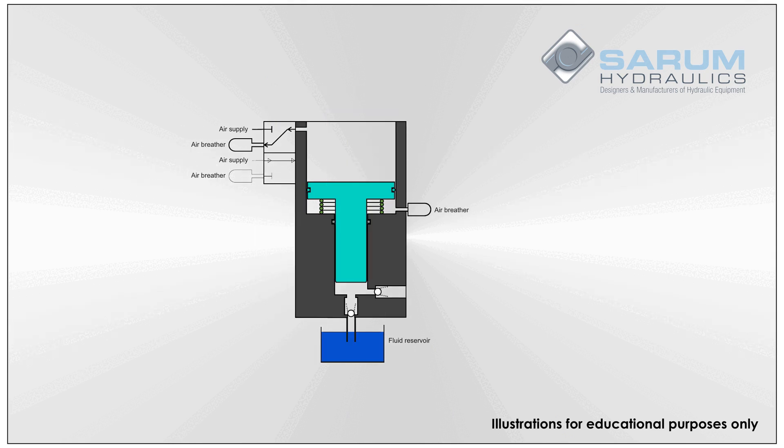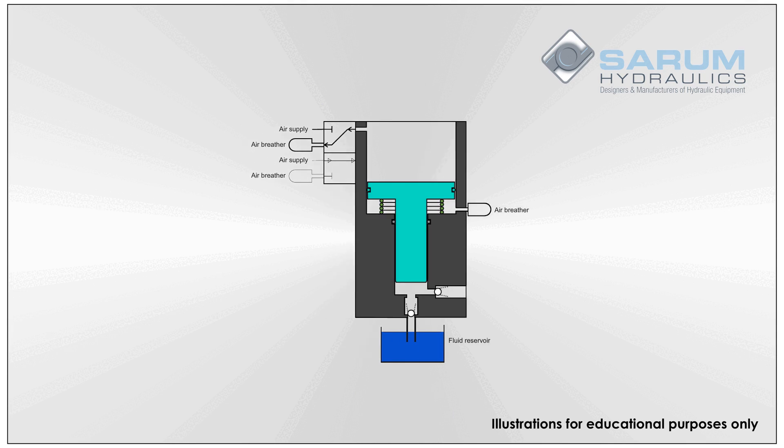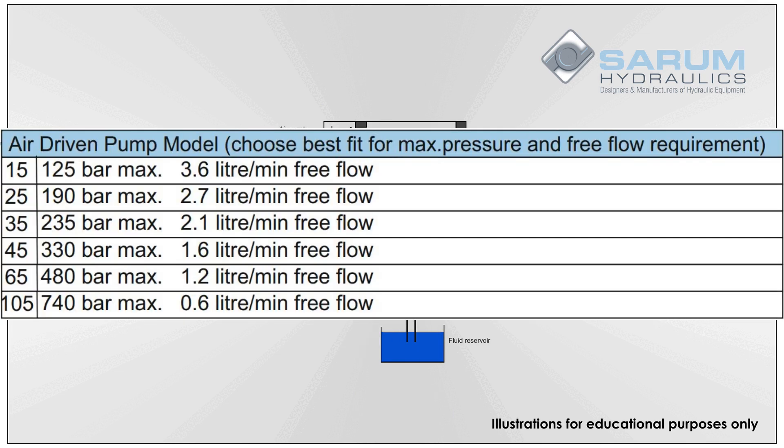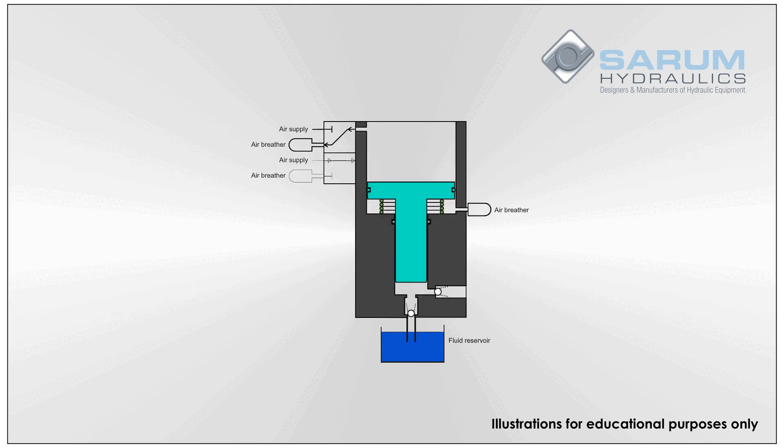Our pump models run right up to 105 to 1 ratio. That gives up to 740 bar of hydraulic pressure from a standard shop air supply. At the other end of the ratio scale you get up to 3.6 litres per minute hydraulic output at free flow. This is how in principle the air driven pumps work.